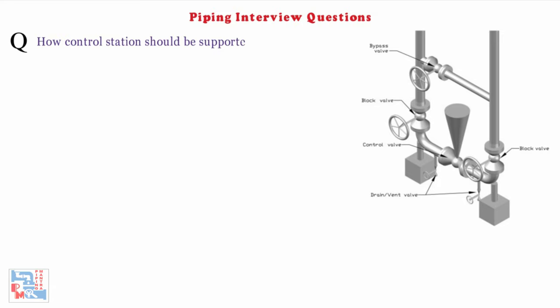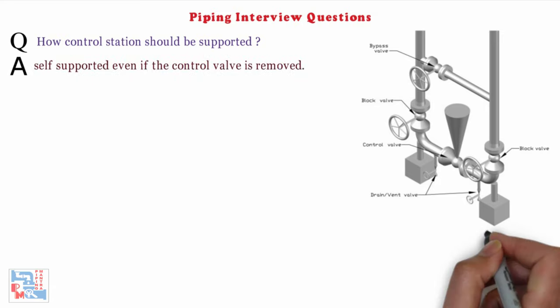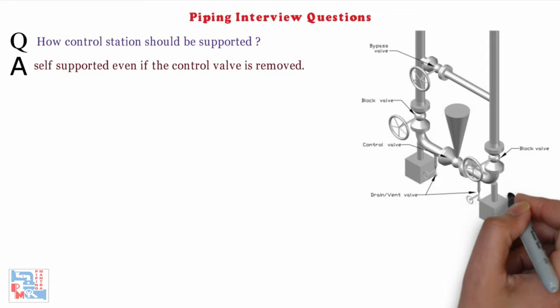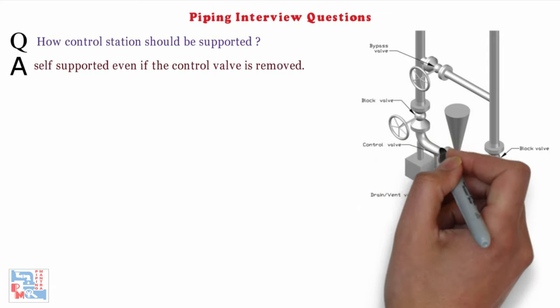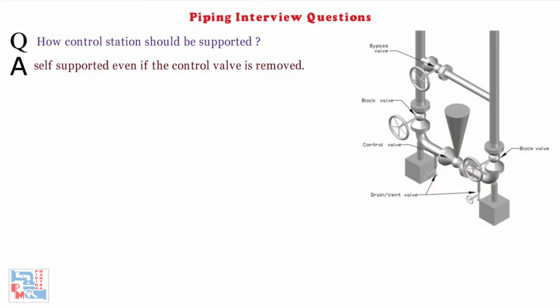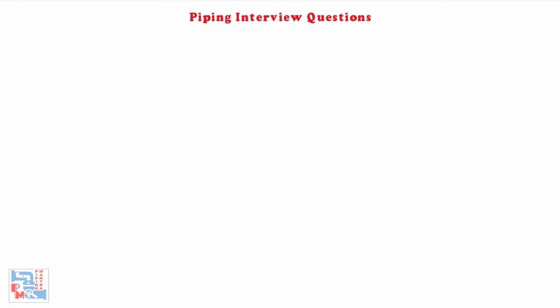Next: how should a control station be supported? It should be supported in such a manner that the control station piping is self-supporting even if the control valve is removed. Normally, control stations are supported on exit side elbows of the bottom run of the control valve.